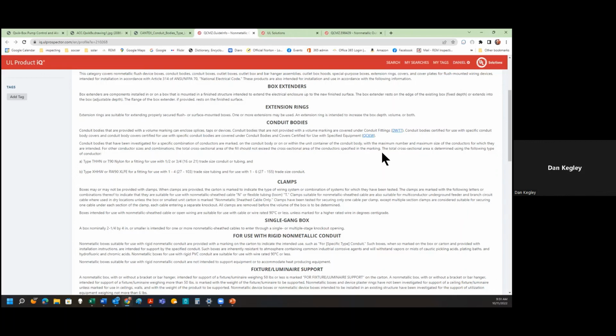That's pretty common because 4-aught aluminum is the largest size you might see for a residential 200-amp service. And so a 2-inch LB, it says 3 4-aughts is the largest conductors that can be inside for the box fill of that. So that limits the size of the box fill capacity based on just having those 3 4-aught conductors inside there based on what this UL listing is. So this UL listing is what limits the size or capacity of that box, or of that conduit body, sorry. So anyway, just a quick rundown of where all this information kind of draws from.